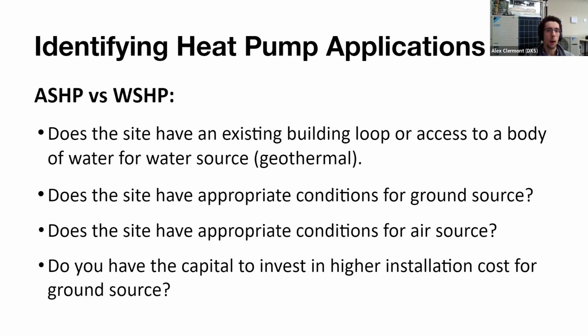So we talked a little bit about this, but how do we actually decide between air source and water source? Oftentimes the water source option tends to be a little bit more expensive, but does tend to perform slightly better. Actually, not as much as you think, but it is a bit better than air source in terms of operational costs, as you're rejecting and absorbing heat from a more consistent source in the ground. Now, here's a question to actually ask. If you have an existing building, does it have any access to a geothermal loop? If you're looking at a downtown Boston building, there's a chance that this is not even an option.